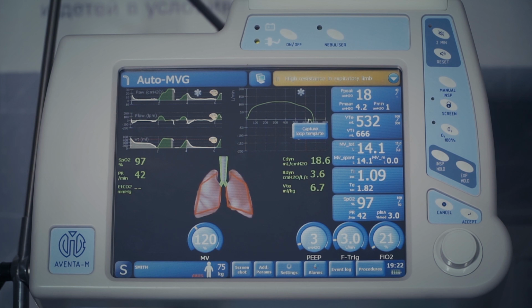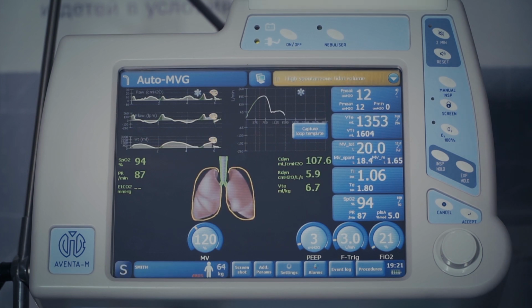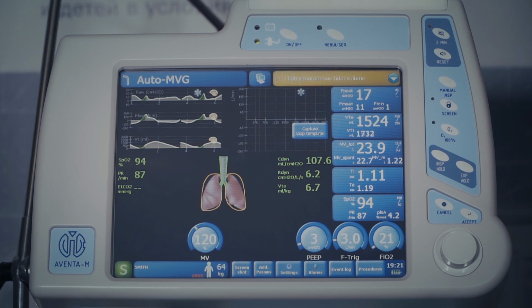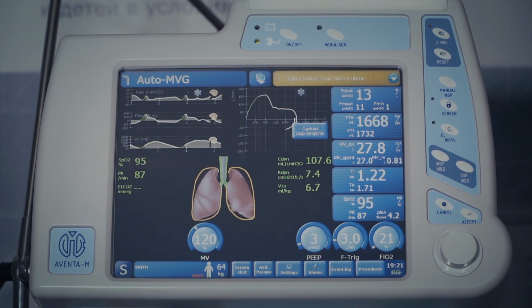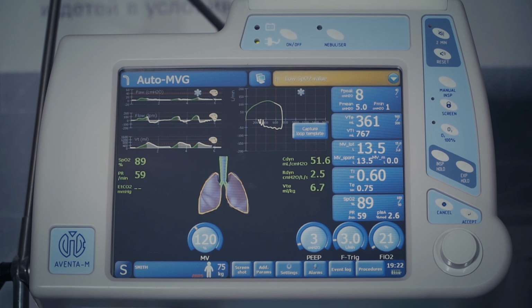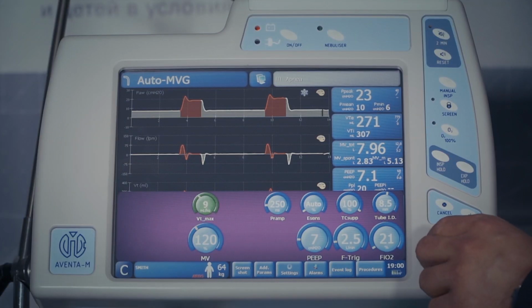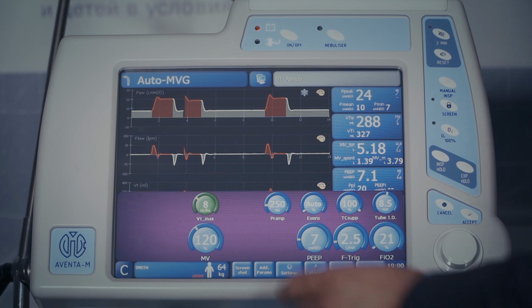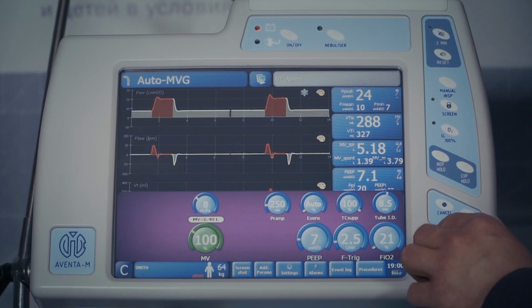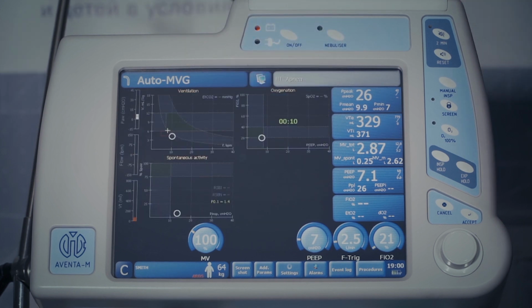In this mode, the main controlled parameters include minute respiratory volume expressed in percent of the normal value calculated based on a patient's ideal body weight, PEEP level, and percentage of oxygen in the respiratory gas. An important additional parameter is the respiratory quotient VT max. It is preset in milliliters per kilogram of the ideal body weight and limits the maximum respiratory volume. Operation of this mode is demonstrated in Window Ventilation Map.